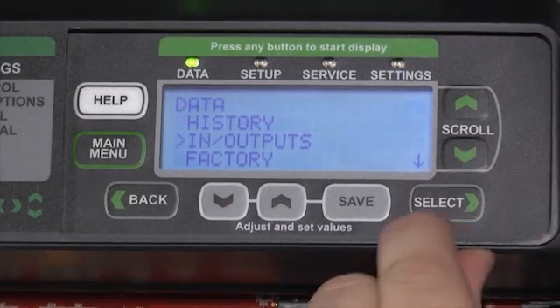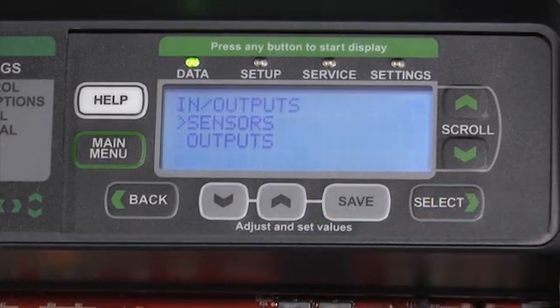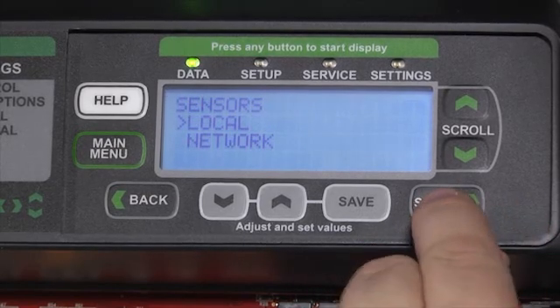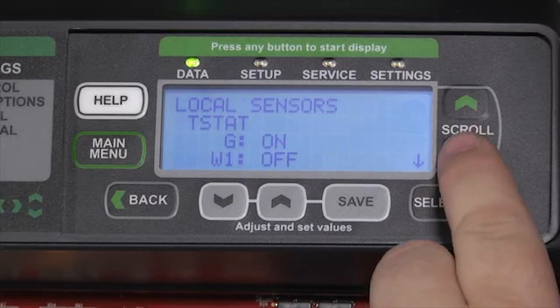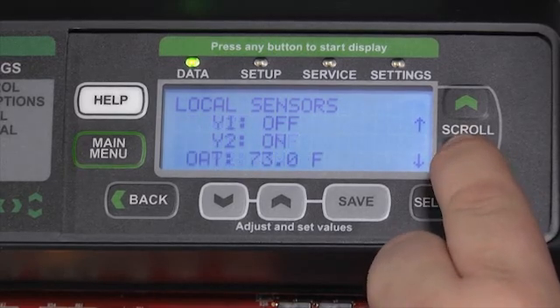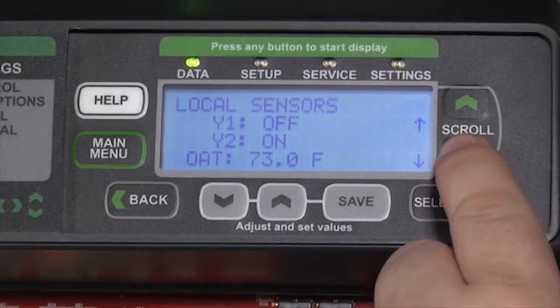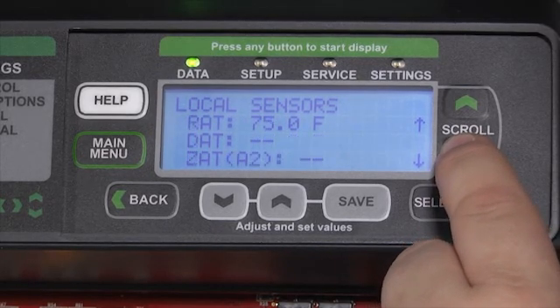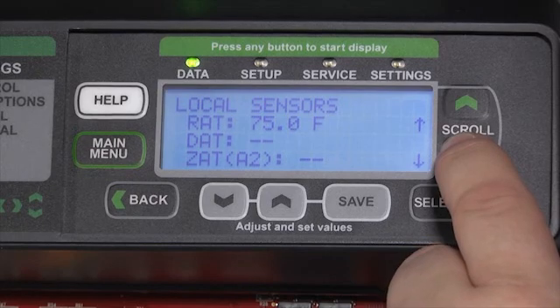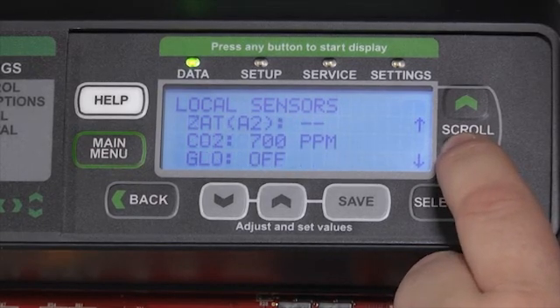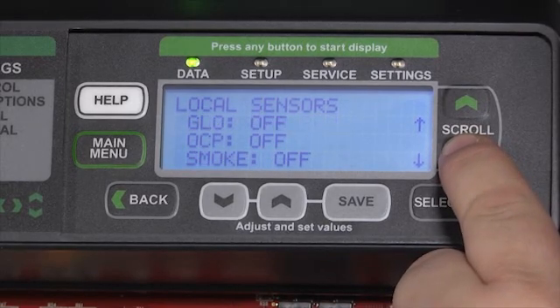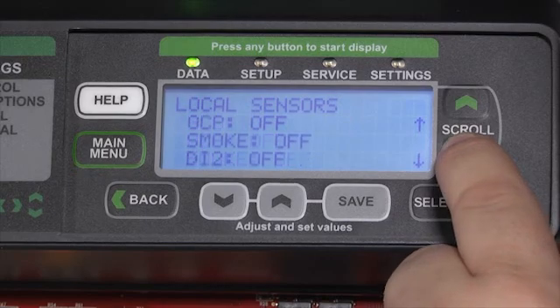We can look at the condition of all the inputs and outputs connected to the machine, such as the local sensors, which will tell us the condition of the thermostat if connected, tell us the temperature sensors, if we have discharge air temperature sensors, or if we have zone temperature sensors that would display their temperature as well, CO2 sensors, your global connection, your occupied status, as well as if the smoke detector is off on alarm, or if the discrete inputs are active.